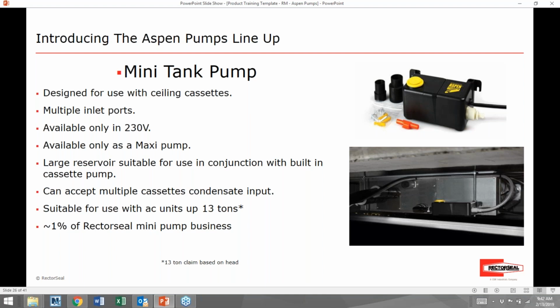A few of the drawbacks here is that the Mini tank pump is only available in a 230 volt application, which will accept 208 to 230. And it's only available as a Maxi pump, so it's going to be a little noisier than our Mini pumps. But that shouldn't be that big of a consideration because it is designed to work with a ceiling cassette, so it would be installed above a drop ceiling or in an attic of some kind. So you have some insulation there from noise.